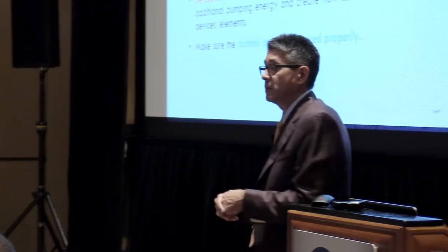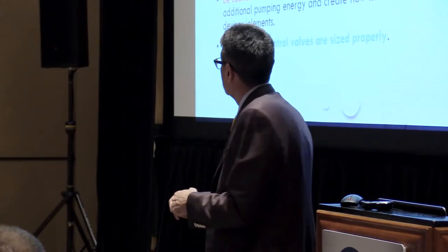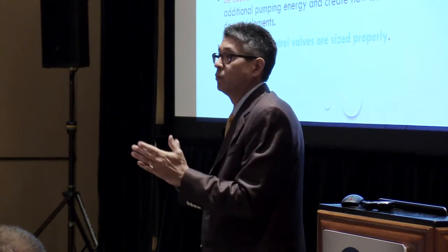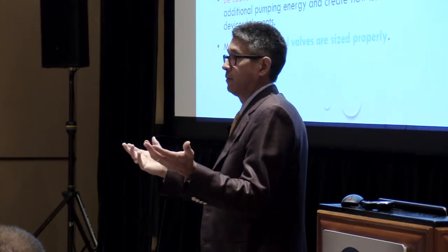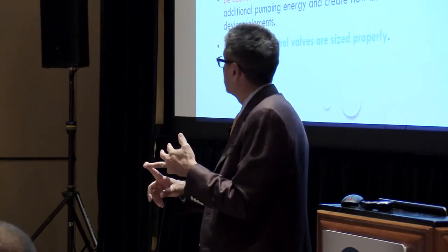utilize that, trend them on the DDC system. Get an idea of what's heating, what's not heating, where you have problems. It gives you a great idea of what's going on. You trend that with the control valve position, you got a really, really good idea of what your system's doing, along with your DP set point and your VFD speed.